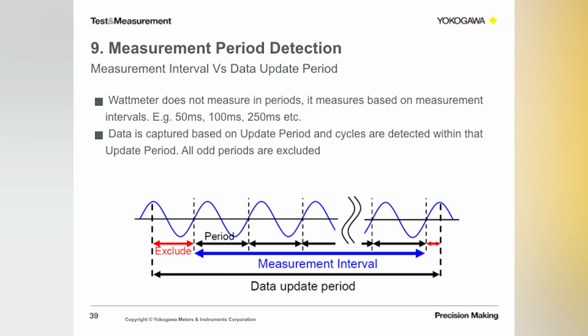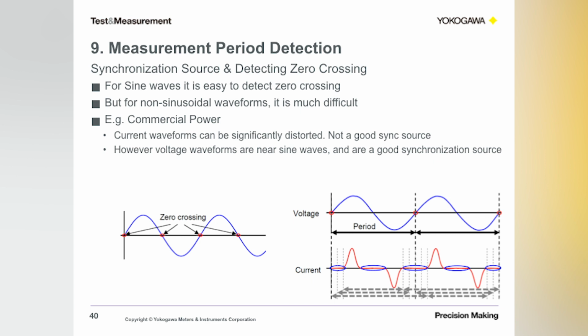When it comes to power measurements, it's important to detect the period. Now, how does the instrument detect the correct period of that incoming signal? Well, you do that by either using a good synchronization signal and maybe some filters if needed. For sine waves, it's easy to detect the zero crossing, but for distorted waveforms like current signals of commercial power, it's a little difficult. However, the voltage signal is a lot cleaner, and that can be used as a good sync source.